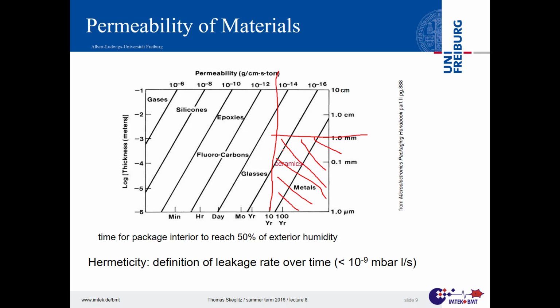You have to know that this is then measured as an integral part. So you put a device into a machine and measure whether gas leaks out, because you cannot measure water that well. And then you take helium, because helium is not that available in air.